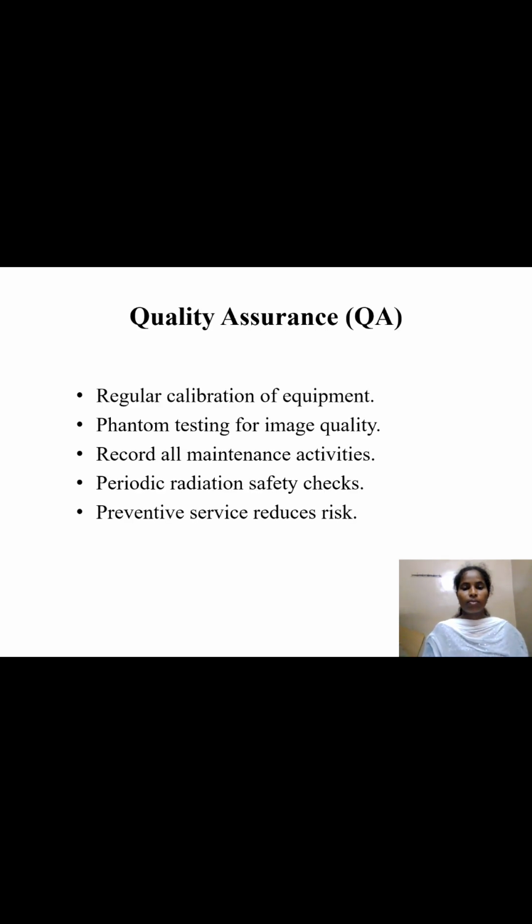Next one is quality assurance. Quality assurance ensures equipment is safe and functioning properly. Regular calibration, phantom testing for imaging quality, maintaining records, periodic safety checks and preventive maintenance reduce risks and ensure reliable operations.